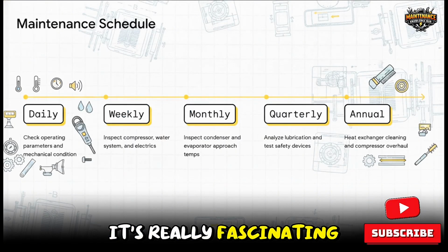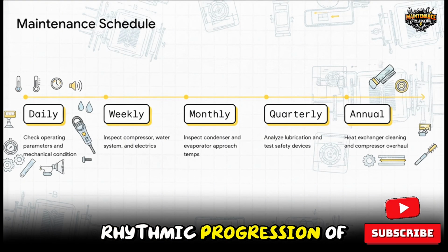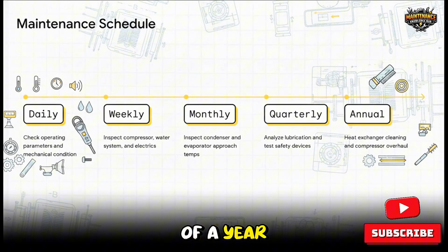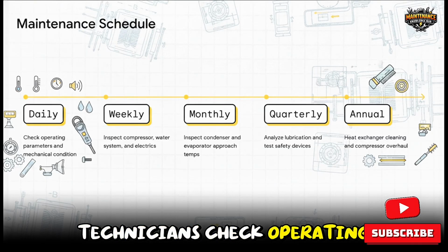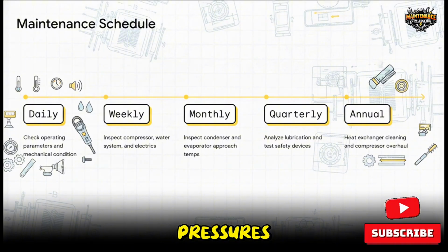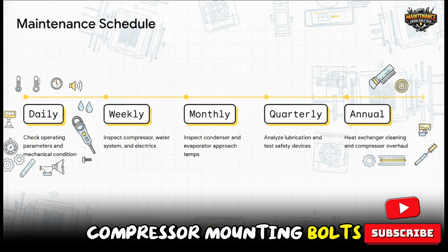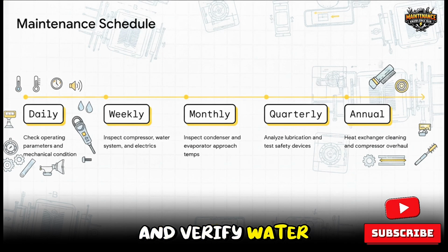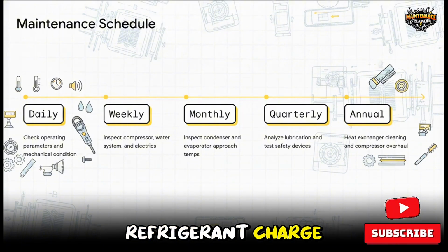It's really fascinating to see how these checks build into a rhythmic progression of care over the course of a year. On a daily basis, technicians check operating parameters like temperatures and pressures and just listen for unusual noises. Weekly, they inspect compressor mounting bolts, check motor currents, and verify water pump operations. The monthly maintenance gets a bit deeper, inspecting condenser and evaporator approach temperatures and checking the refrigerant charge.